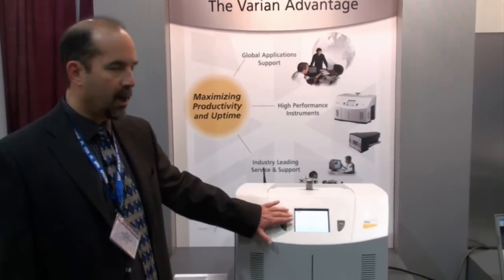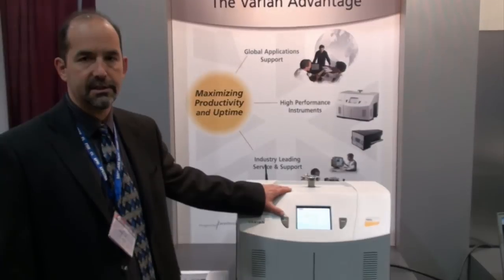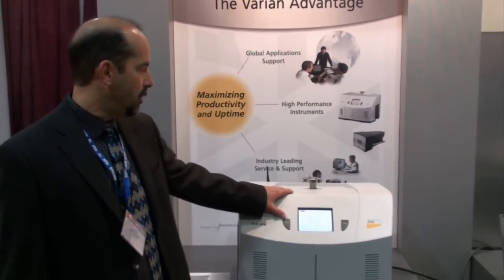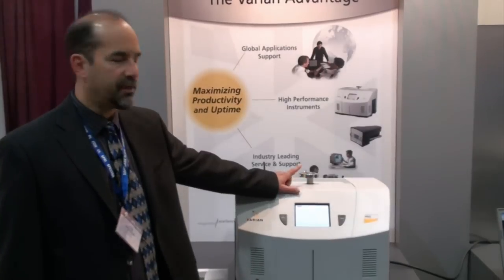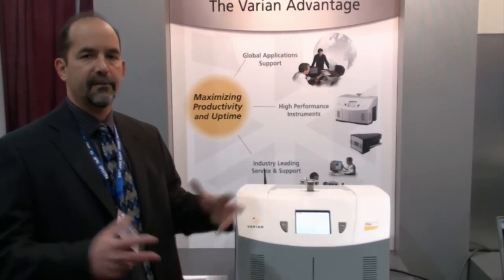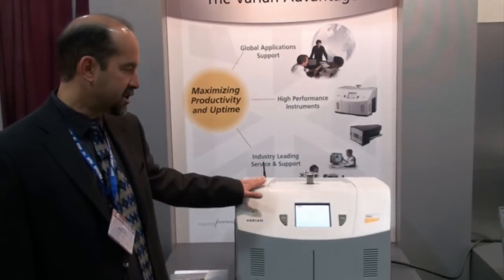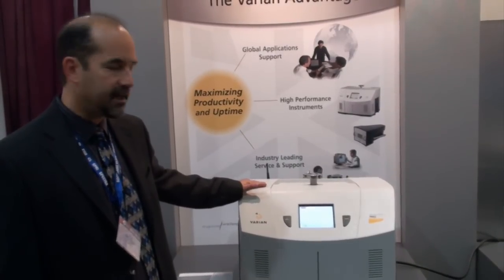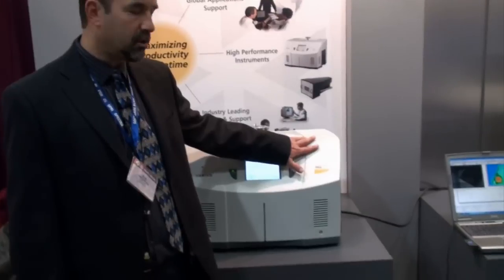It also can go up at 8 decades of leak rate, so it has a wide variety of uses in the vacuum industry. We can also convert it easily with what we call a sniffer device to pick up leaks coming from inside a system and leaking outwards. It's a very versatile unit, very well priced and competitive. The PR02 is portable and has a small rotary vane vacuum pump in it that pumps on the test port.